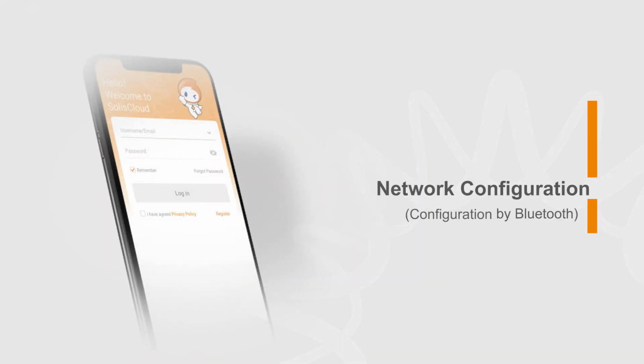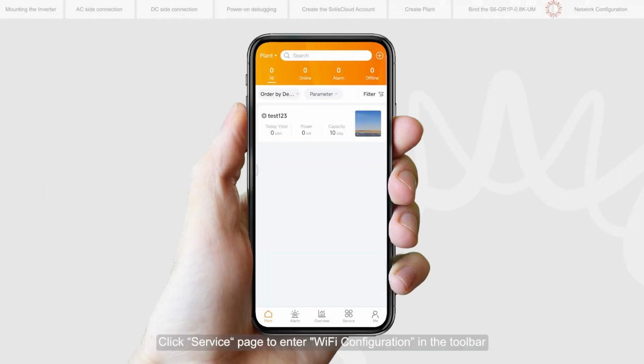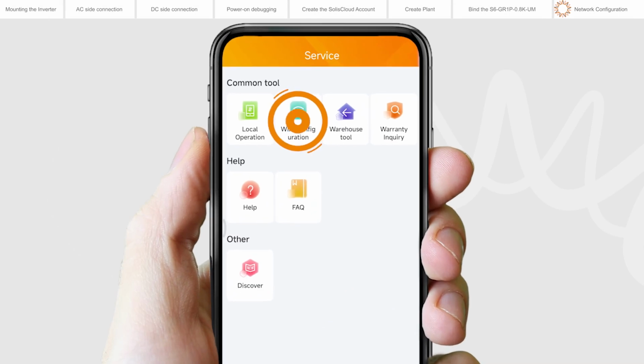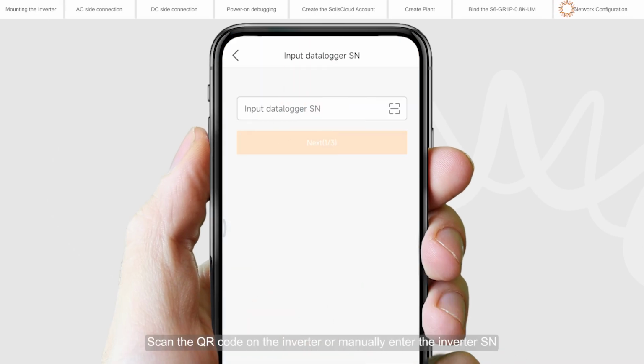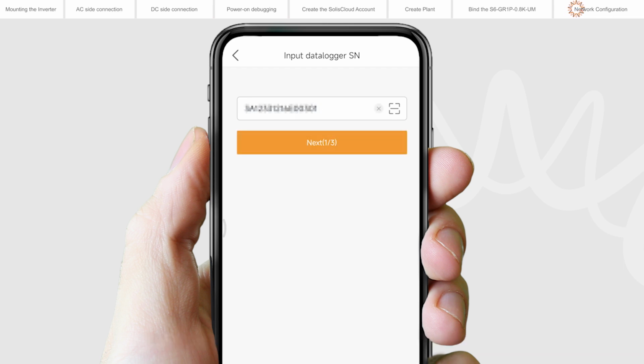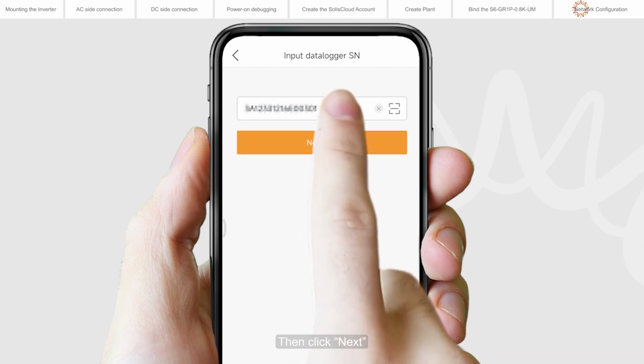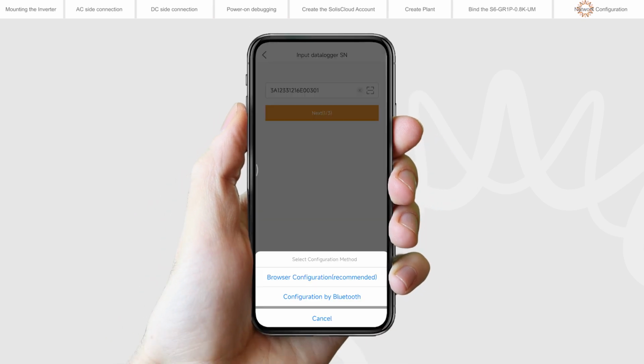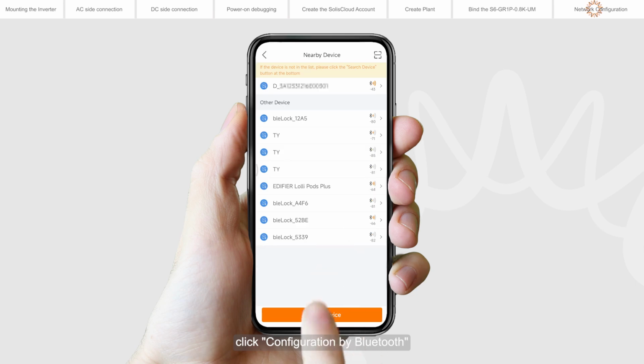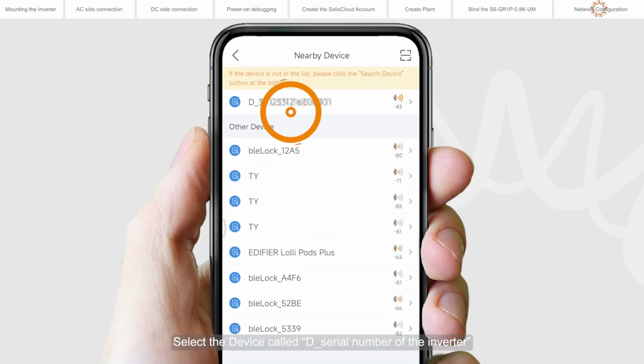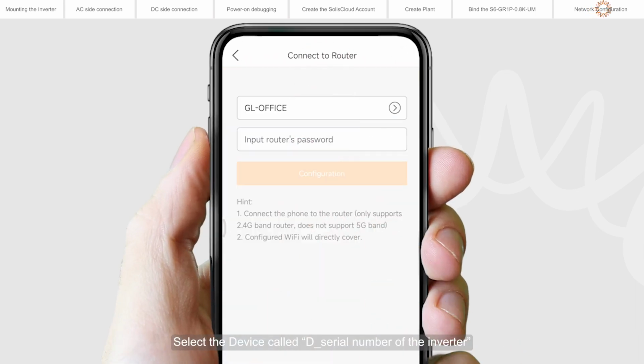Network configuration. Click Service page to enter Wi-Fi configuration in the toolbar. Scan the QR code on the inverter or manually enter the inverter SN. Then click Next. Choose the configuration method. Click Configuration by Bluetooth. Select the device called D_ serial number of the inverter.